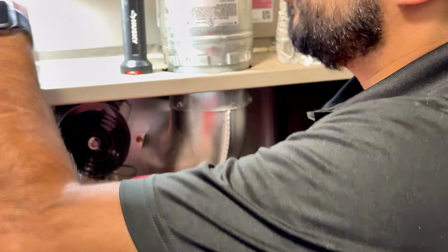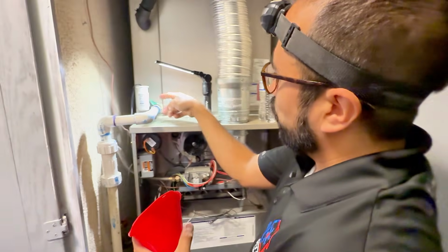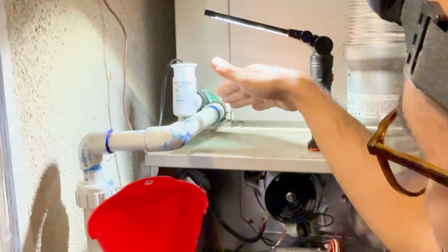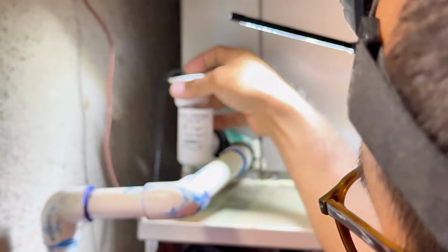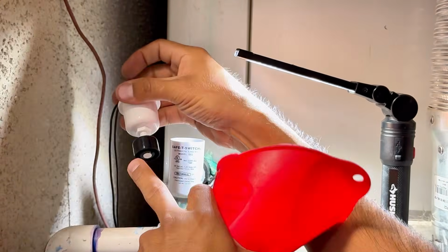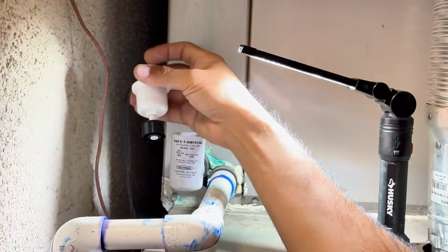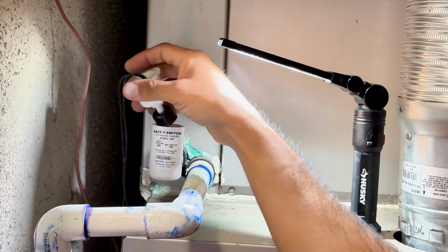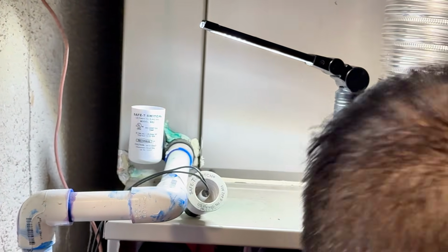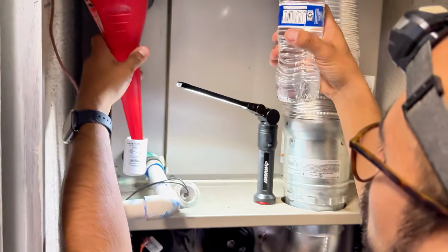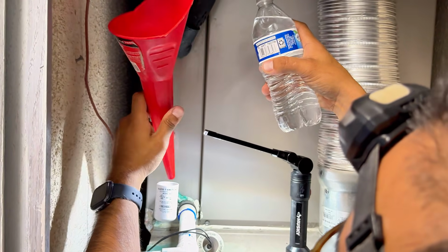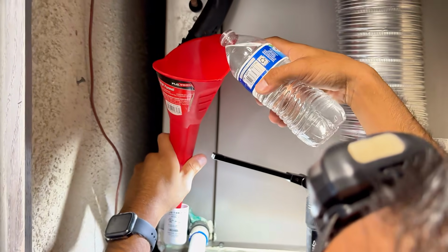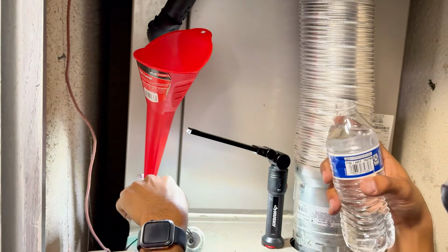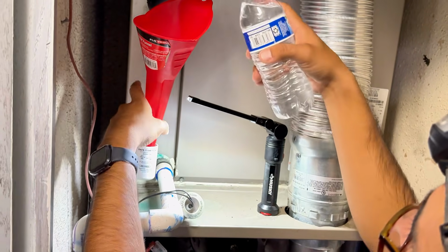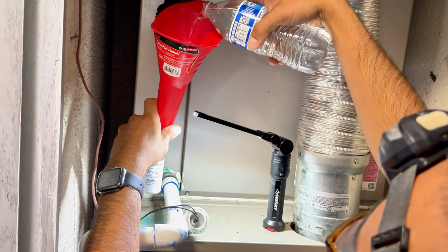If water rises, it can't drain from here because it's going to go to the lowest point first. But if that gets blocked, it'll come out from the secondary, and if this goes up, it will shut off the condenser or turn off the thermostat. I don't know how they have it set up here, but to make sure it's working, I'm going to put a funnel and pour some water in — it should not back up. I should be able to hear it coming out through here and condensating. So let's go ahead and put some water.